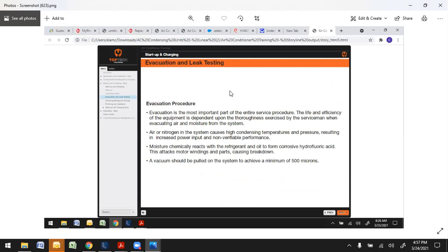Now we'll get into evacuation and leak testing. This goes over not just this particular class, but all classes. Evacuation is the most important part of the entire system procedure. The life and efficiency of the equipment depends on how it's set up, and the thoroughness exercised by the serviceman or installer when evacuating air and moisture from the system.